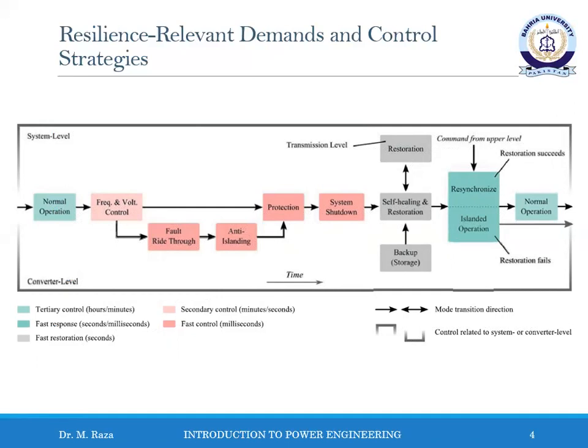Beyond this short period, the protection device scheme should operate and activate the anti-islanding operation. When the grid is completely out of service with the application of protection devices, the distributed generator may still power the critical loads. Alternatively, together with the backup energy, they can help to restore the distribution grid. In this case, coordination between the transmission system level or the storage system and the distribution system may be necessary. Once the fault is removed from the transmission system or within the network, the remaining distribution grid can be resynchronized with the network and start working normally.